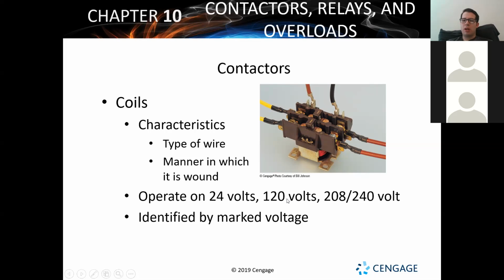The main thing is you can have it where, like it's saying here, the coil is either going to be 24, that's typically for residential. You're going to see a lot of 24 volt coil systems. I've never run across a high voltage contactor coil in a residence. The only time I've seen 120 coils is on commercial rooftop package units. And then the 208, 240 is when you're dealing with more of your commercial, industrial size kind of stuff, large commercial, not just, oh, we've got a package unit on the roof for one office building, as opposed to, hey, we've got a whole processing plant or a massive office building that's 18, 20 stories, something like that.